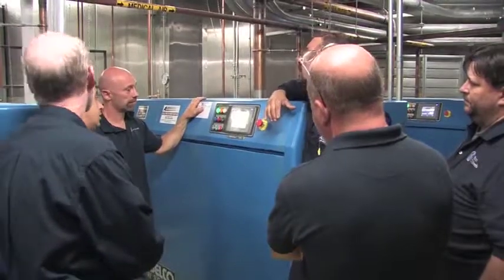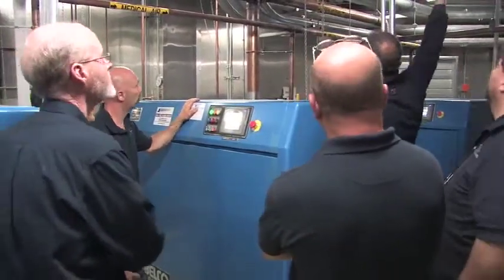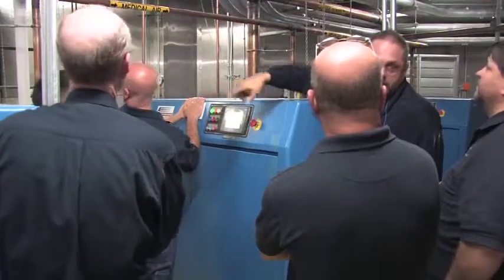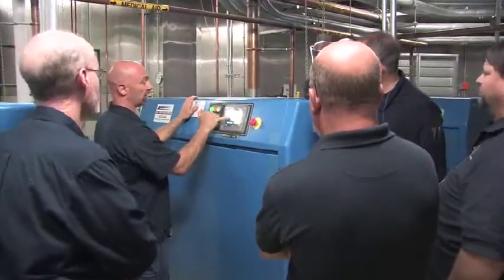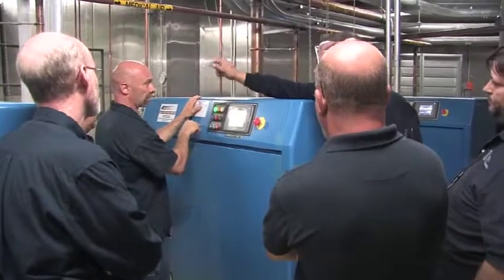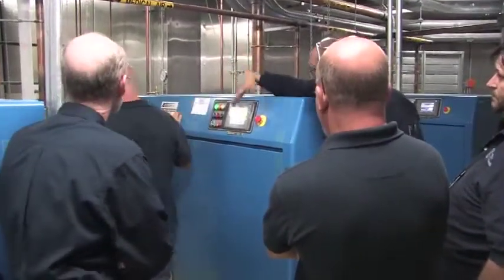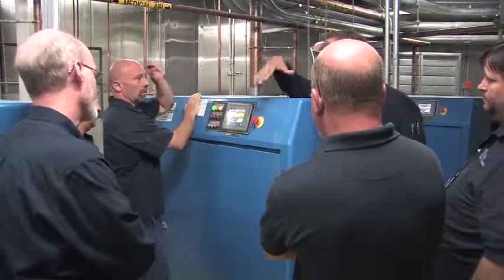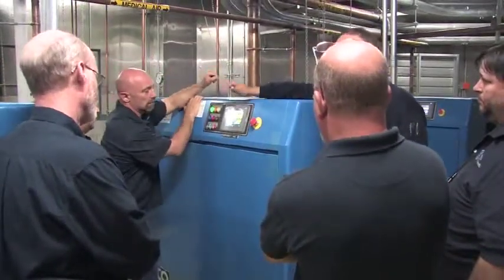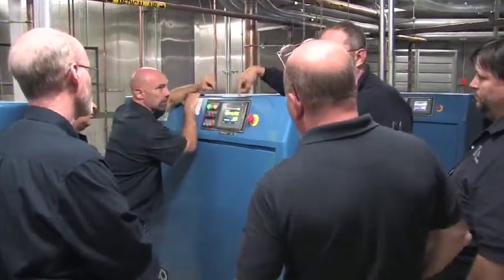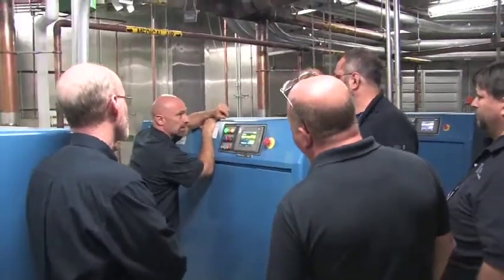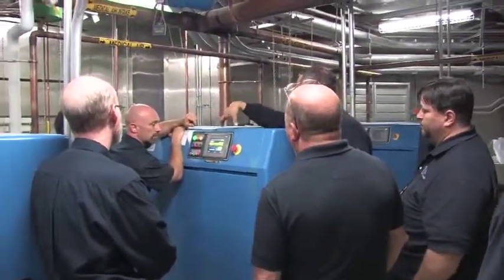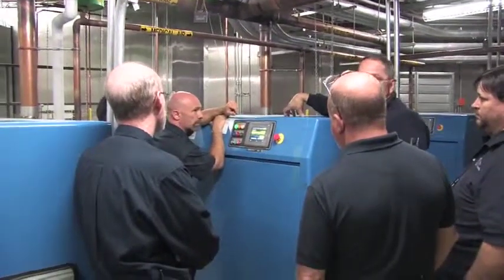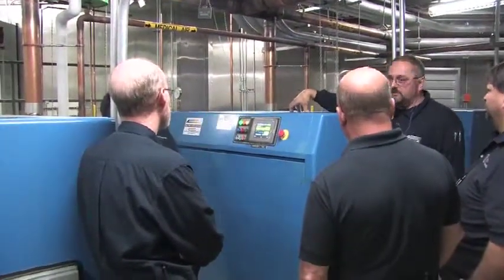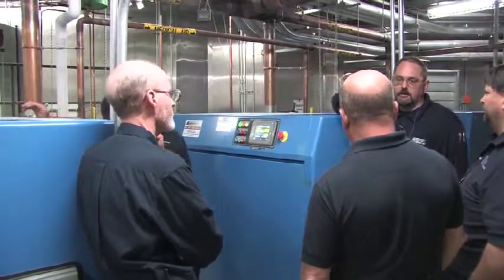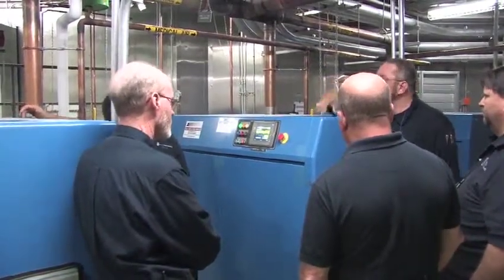Your intake pipe is coming in from outside and you're dropping into each one on the flange connector there. Is this inlet for this machine only? That's the inlet for this machine. Each machine has its own, and again, all the normal controls are on each one. You can look at the sequencer from this. We'll get to that. You can see the sequencer front screen, so to speak, from each of these machines. However, the only machine that you can log on and make a change to the sequencer settings is that one. You can't make any changes to it from these.